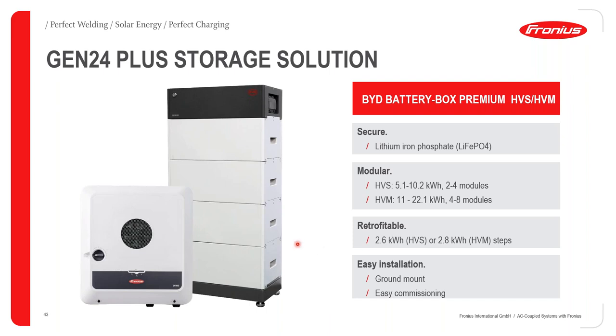Also, please take note that you can have three of these towers in parallel. So in essence, if I take three HVM towers with 8 modules each, I can get a total storage of 22.1 kilowatt hours multiplied by 3, which is around 66 kilowatt hours of maximum storage on the HVM. What's nice to know with the BYD Premium battery is that it allows for ground mounting and also for easy installation and commissioning. Both the GEN24 and the BYD Premium battery are IP65 rated, so they can both be installed outside. They are both waterproof and dustproof.